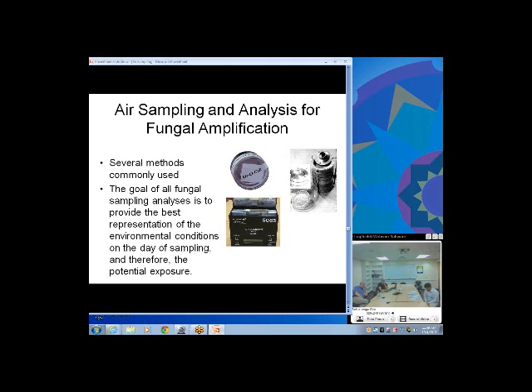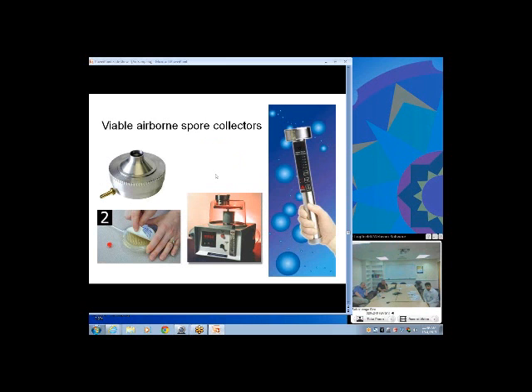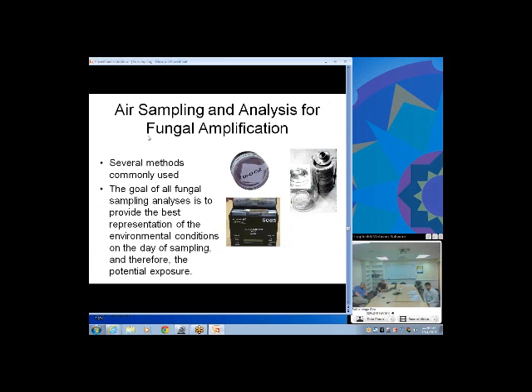We've seen the Allergenco device and there are competing cassette-type collectors, commonly used to sample indoor spores. Non-viable devices produce a result with a spore attached to a glass surface — either a glass slide or a small glass-mounted material coated so the spore sticks to it. You take it back to the lab, put some stain on it to help define spore characteristics, and count how many spores you see under the microscope.